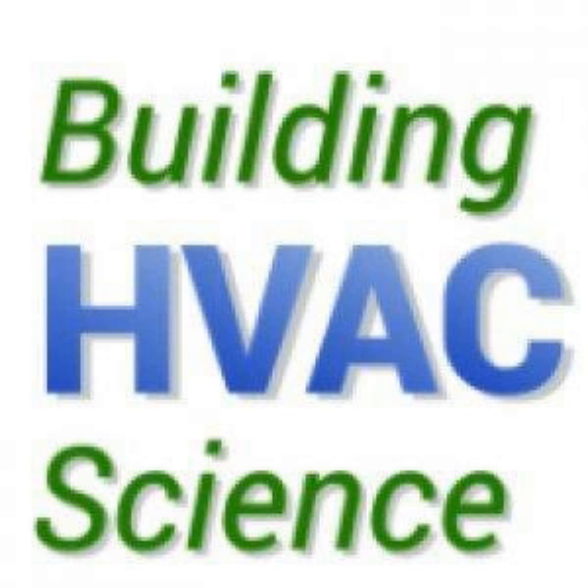You want warm air. That's an interesting thing, because I've actually talked to a couple of water heater manufacturers about doing that very thing and tying it in with HVAC systems, because I thought the same thing would work really well. I also have a heat pump water heater in my basement and had planned to duct that into my return so that I mix it with the house better. The HVAC fan is extremely powerful in comparison to the fan that comes with the heat pump water heater. And so using that fan to suck air is a good idea, because too much air is not a problem. Too little air is. So if you try this on for size, I'm curious what you think about this.